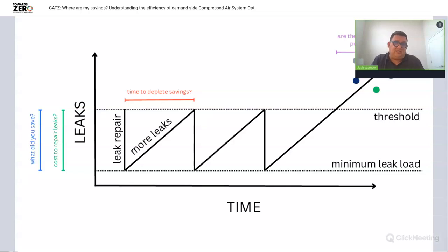There are plenty of scenarios where the customer calls you and says, hey, we don't have enough compressors to maintain system pressure, we need more air. If you audit the supply side, you will see pressure fluctuations. You'll see that your demand side is higher than your supply side. And depending on what they allow you to do inside their facility, you might not have any other way to go than to just sell another compressor. So please understand that I am not trying to be disrespectful to anybody, especially for doing their job.